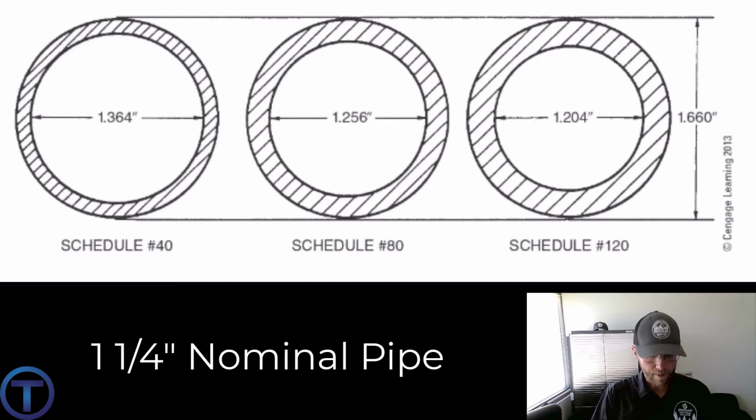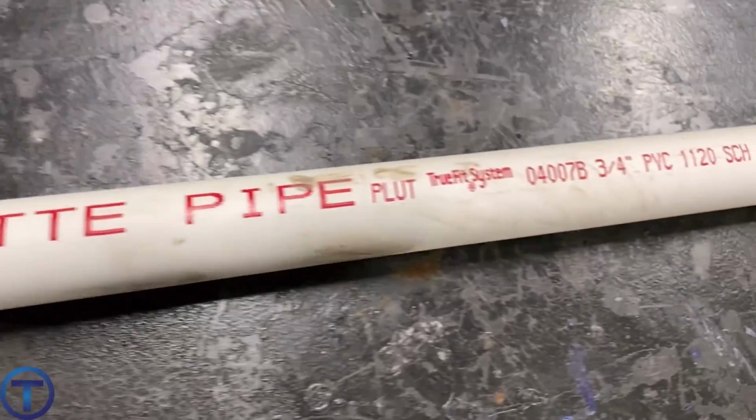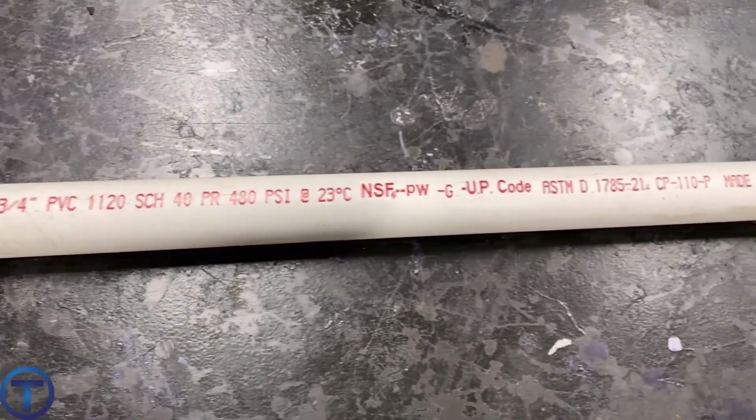Look over these diameters. The outside diameter for a plastic 1 1/4 inch pipe is 1.660 inches. That's bigger than 1 1/2 inch. So what you don't want to do is get your measuring tape, measure the outside diameter and say, oh, it's more than 1 1/2 inches, this must be 1 1/2 inch pipe. It's not. And of course, you can look at the printed words on the side and read exactly what that pipe size is if you don't know.